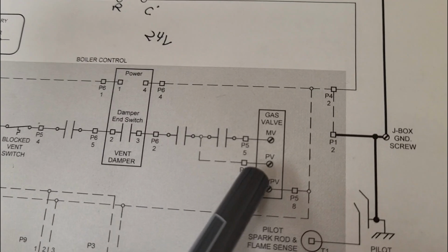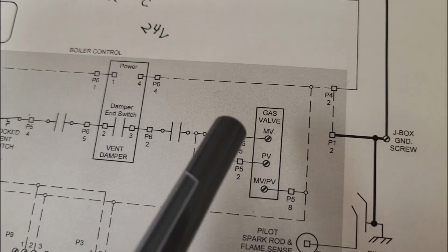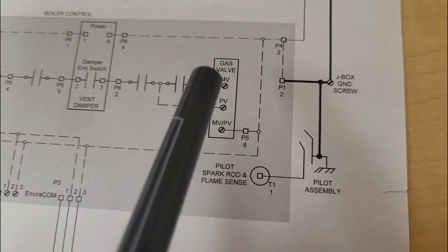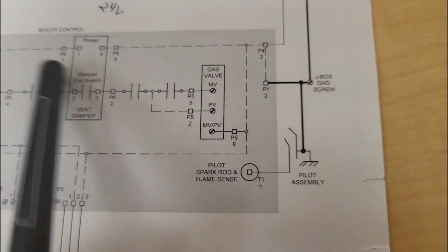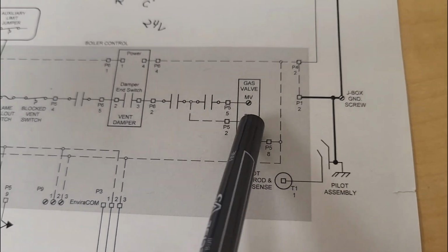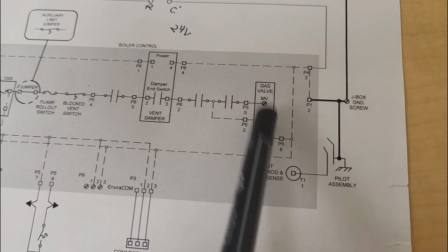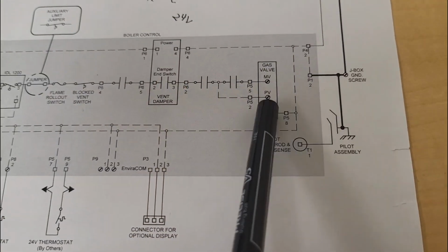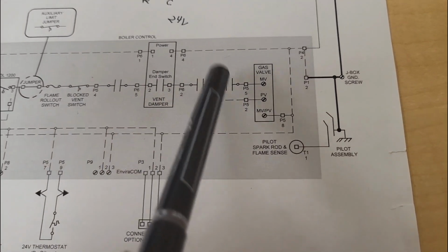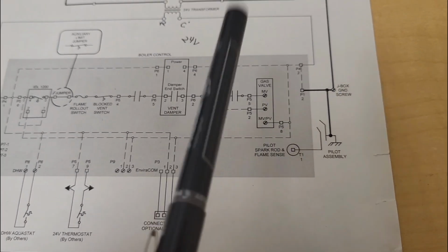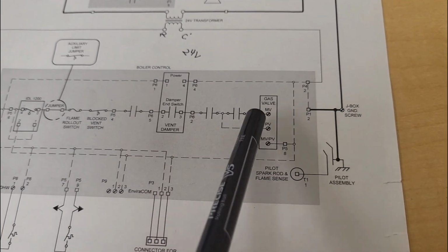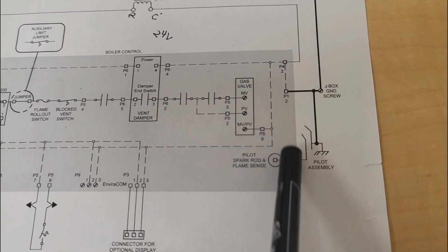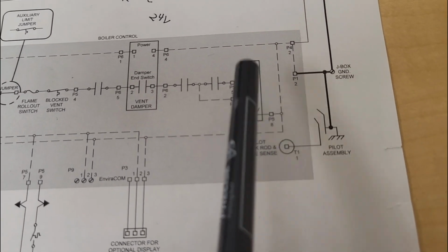Now guys, I want to say 100%, unless you have like an older system, 100%, most gas valves now are going to be spark ignition. You're not going to see hot surface ignition boilers unless you're dealing with certain 90% units. But just to keep things simple, this is an 80% hot water boiler. 100% of the time, you're gonna be dealing with spark ignition, brand new boilers. Back in the day, remember you had, and you probably still see these around, your standing pilot units with thermocouple and all that. Unfortunately, those things aren't as efficient down the line because on a real windy day, the pilot light goes out and now the customer's calling you to come back out to light the pilot. But they eliminated that headache and just went with spark ignition. Spark ignition is the intermittent ignition. This will allow the pilot to only be lit on a call for heat.